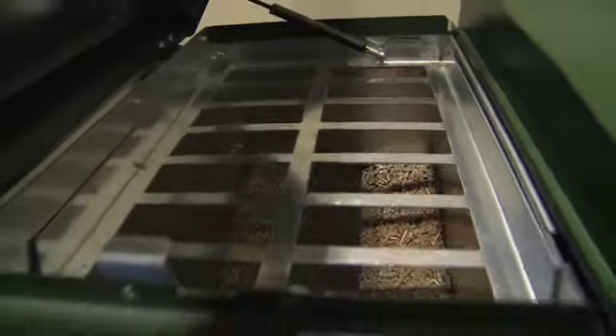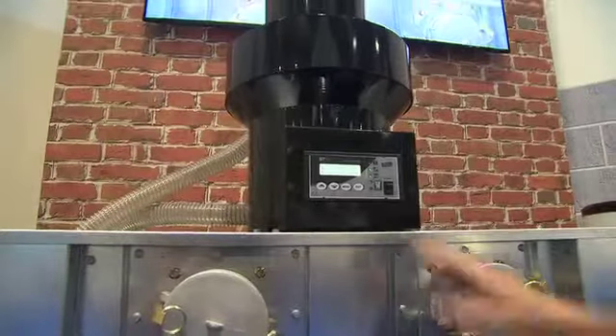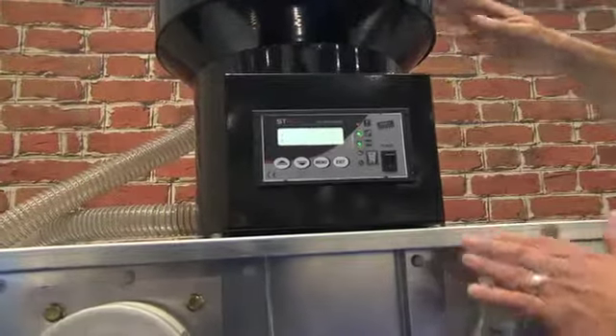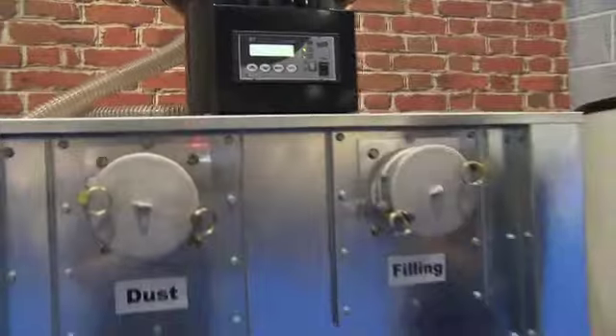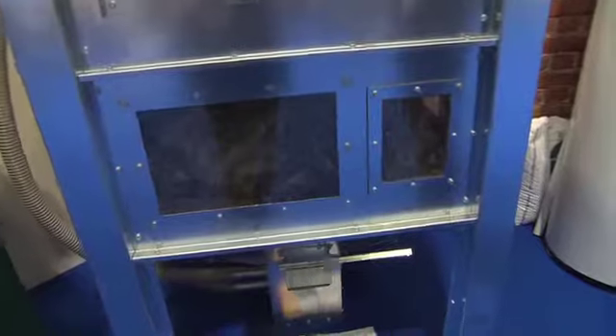Obviously, if you want to automate internal boilers, if you're going to site a boiler inside, we have vacuum systems available for all internal boilers. You don't want to be fitting these on an external boiler. So you can feed by vacuum or an auger screw feed system if you're close enough to the property. We'll demonstrate this running, but bear in mind, this piece of kit is usually sat on top of the boiler. We faked it for today. So you can hear the pellets going in. One good tip, if you are going to use a vacuum system, make the customers aware there is a noise to it. It's a vacuum.